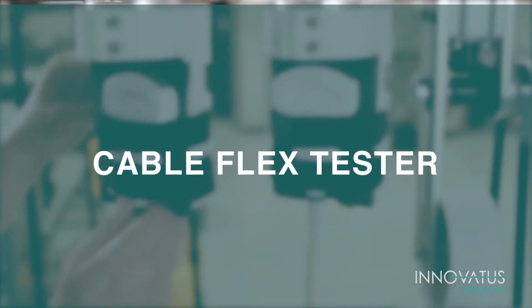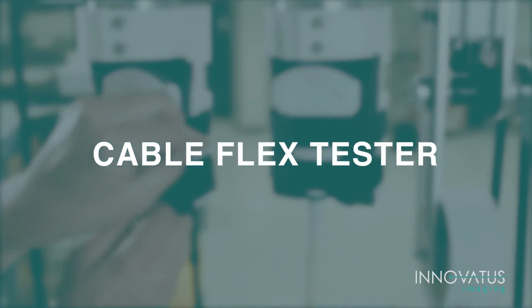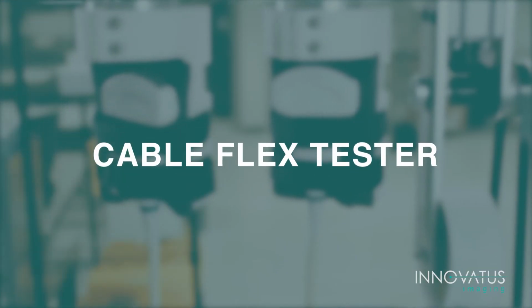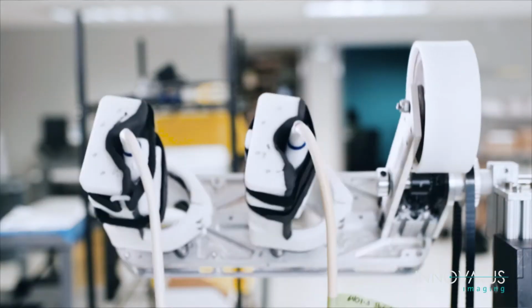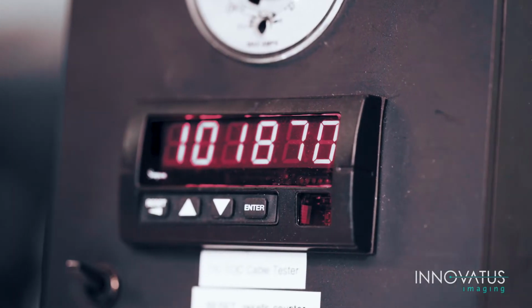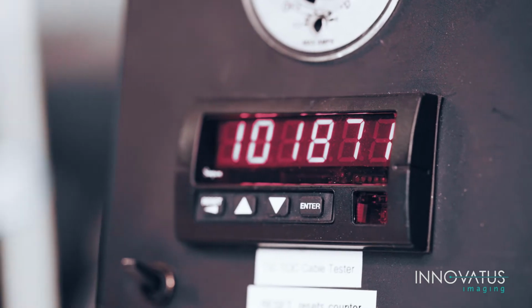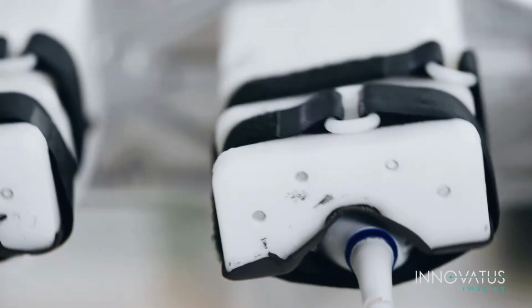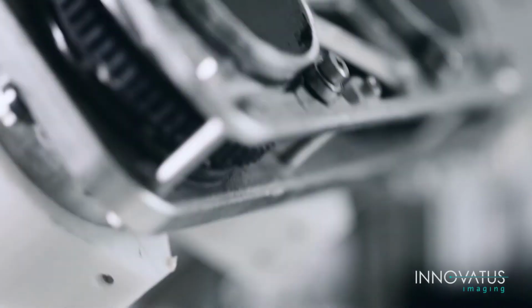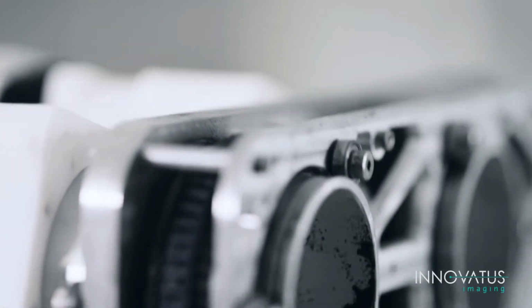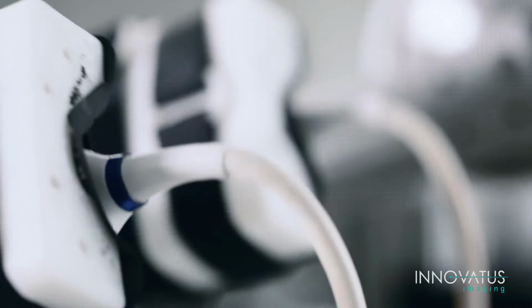A cable flex tester, also known as a tick-tock test, is a great tool for characterizing the longevity and life of a cable. Anytime we repair a cable or a bend relief, we'll often like to qualify them on a device like this to make sure that the product that ends up in the field is robust and that we've provided a sustainable repair. By rigorously testing our designs, both for OEMs and repairs, we ensure that our products are highly robust and will provide an excellent return on investment for our customers.